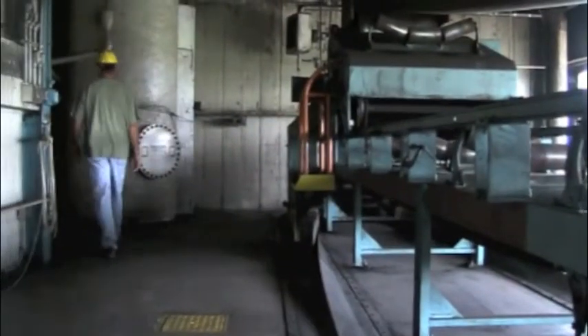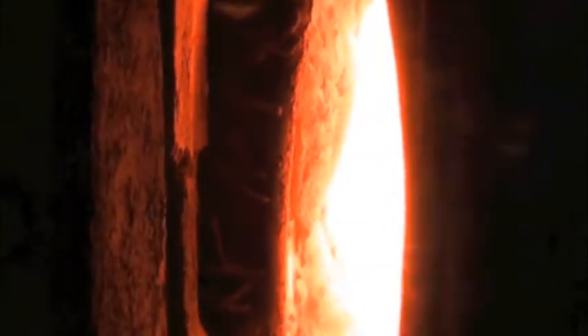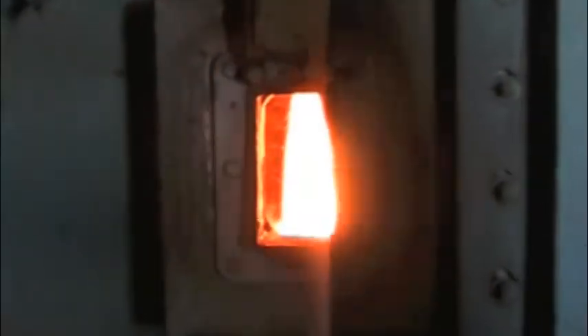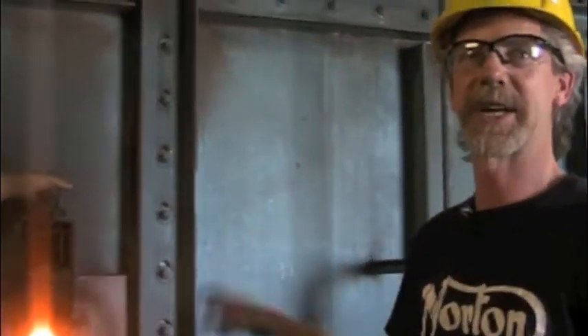Continual maintenance of the facility keeps the unit ready to operate whenever it's called upon. During plant operation, employees continually check on all equipment and processes to keep the unit operating safely and efficiently. Coal's being burnt, coming out of the burner there, and that's where it's producing our heat. There's suction on the boiler — we need suction to keep everything inside, the fuel inside, so it'll get induced draft out the roof. Otherwise, if there's positive pressure on it, we'll have fuel blowing out of every little open crack in the plant, which is not safe.